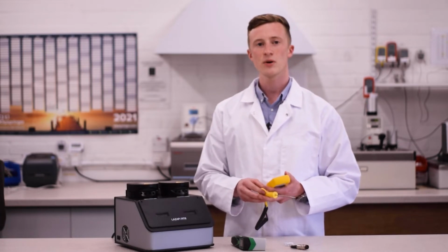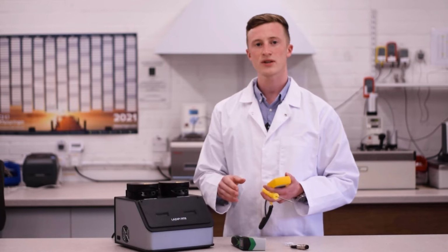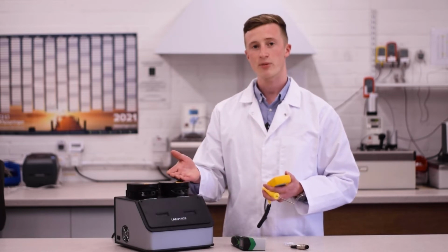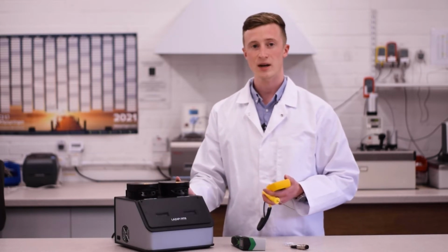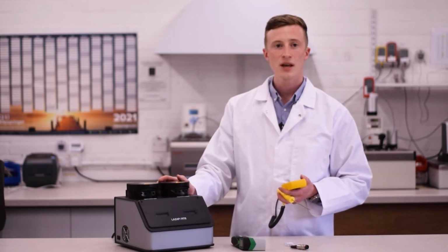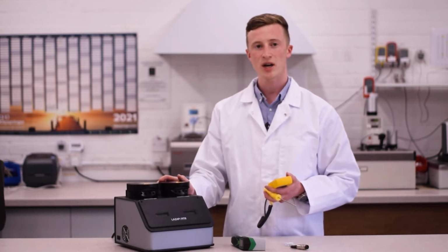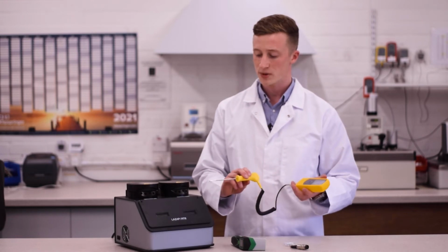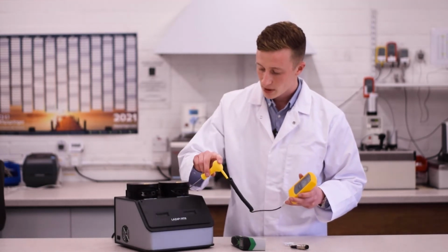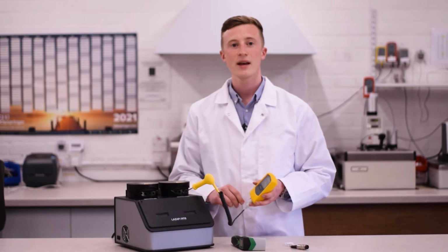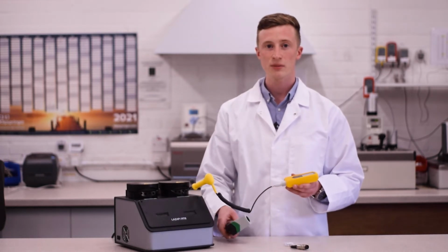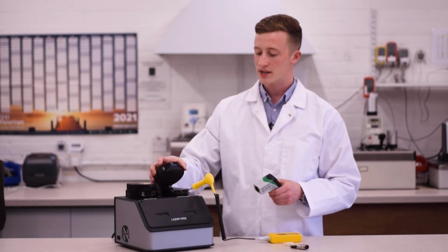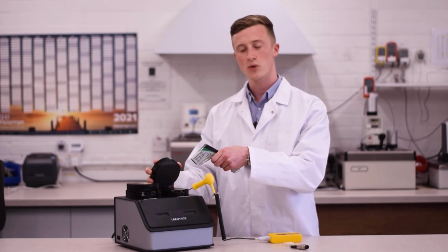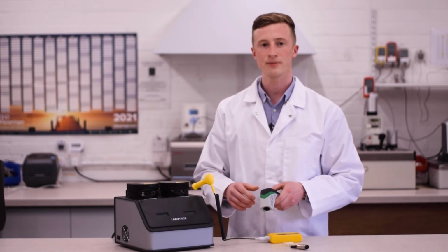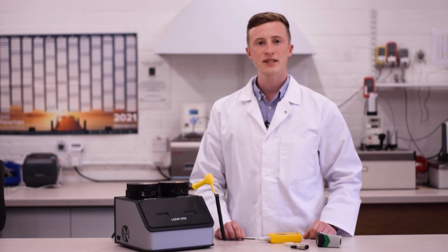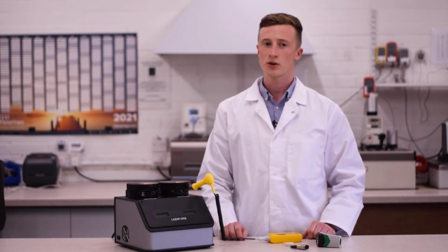Klipspringer recommend the most effective way to meet all of these criteria is with a heat source calibrator, such as the LaserPort 8 calibrator, which I have here. This also gives you the ability to speed up your thermometer checks by checking probes simultaneously in these top ports here, as well as checking your infrared thermometers against a known calibrated medium, which is highly useful for accurate infrared verification. The BRC standard also states results should be documented.